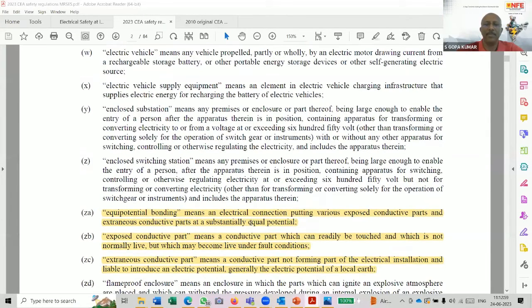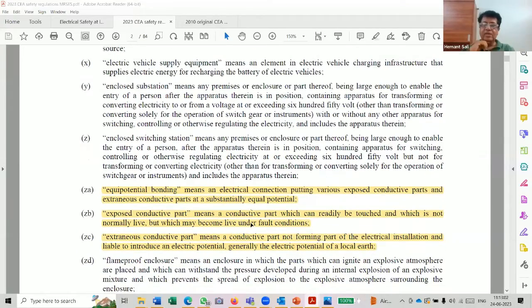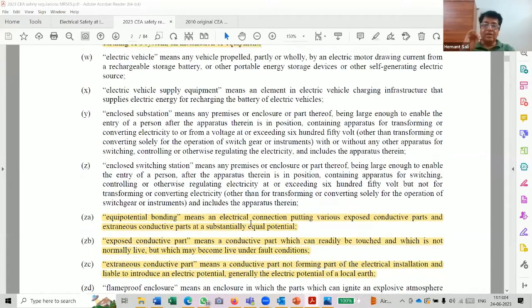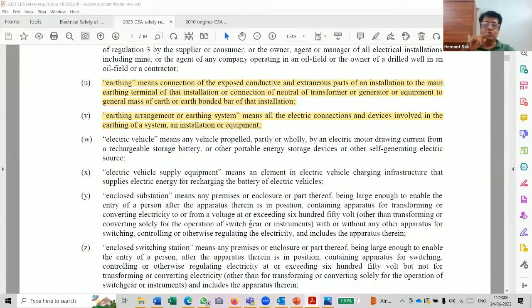Please. See, when they say two distinct connections, it should not be taken as two different earth terminals. It should be taken as two different paths through which the earth connection shall be given. So if one of the earth wires, one of the protective conductors, breaks, at least there should be another path to reach the earth. In that way, it should be interpreted. Actually, it is talking about two connections. The requirement of two connections means two different protective conductors which take you to the earth terminal.